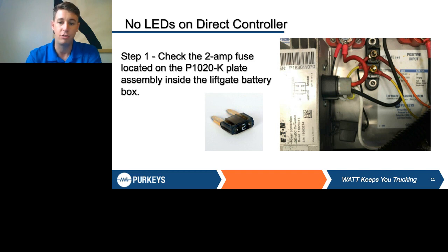As you can see in this picture on the right side of the slide, that's the plate assembly, a close-up view. At the bottom of that picture is the fuse holder, which holds that 2 amp fuse, also pictured on the slide. If this is blown, it will not allow the power signal to get to the controller. All that signal does is indicate to the controller the amount of voltage being read back at the battery box, and tells those lights to come on. If that signal isn't getting to the front, those lights won't come on. So the first thing to check is whether that fuse is blown.